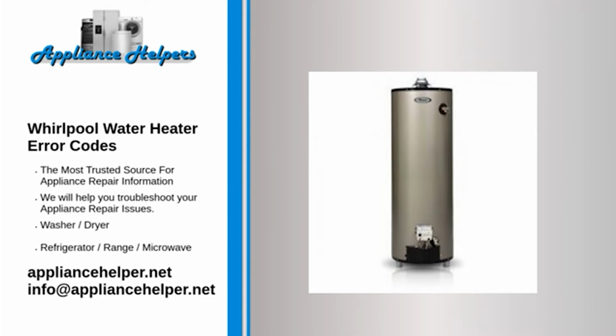Code E02. Problem: water temperature exceeds the high limit. Fix: switch the two house circuit breakers dedicated for the water heater to off and then press the reset button located behind the control panel on the water heater. Flip the house circuit breakers to the on position. If the error returns, call a service technician for assistance.